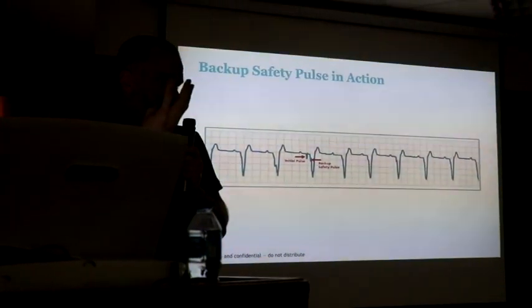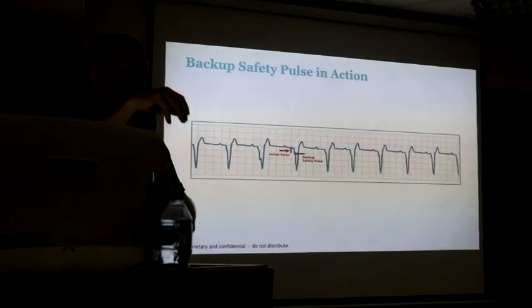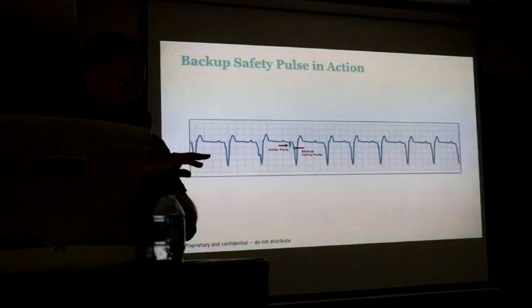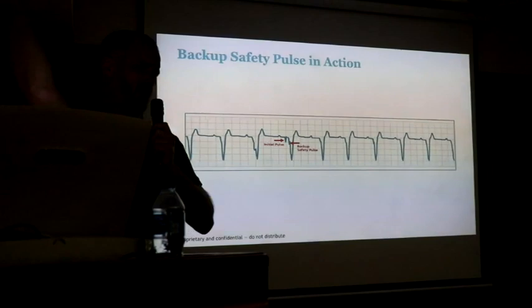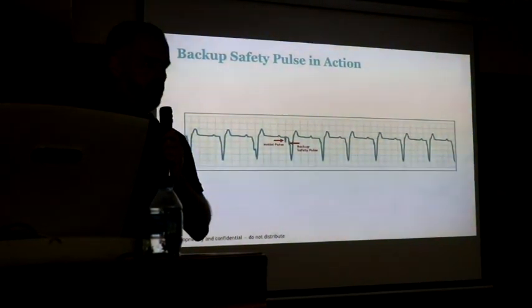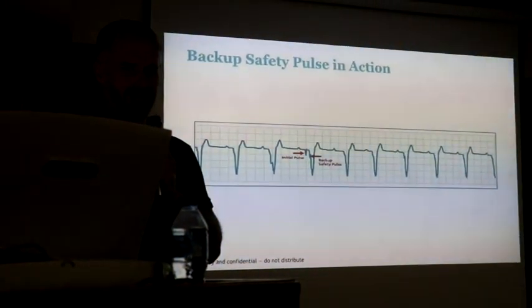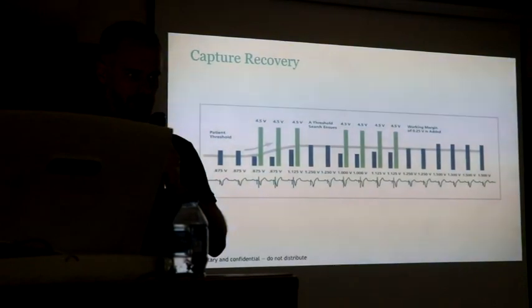So you're saving some battery current, you're saving battery, making the longevity better, but more importantly, it's a safer setting for the device, for the patient, right? Because the patient cannot lose capture unless the lead comes out of the heart. Right? If the lead comes out of the heart and is in the SVC, then yeah, it's not that good. It's good, but it's not that good, right? Okay, does that make sense now?